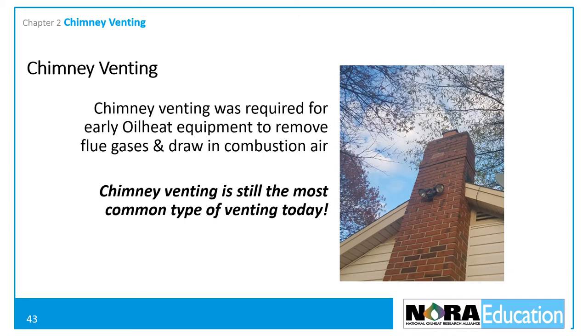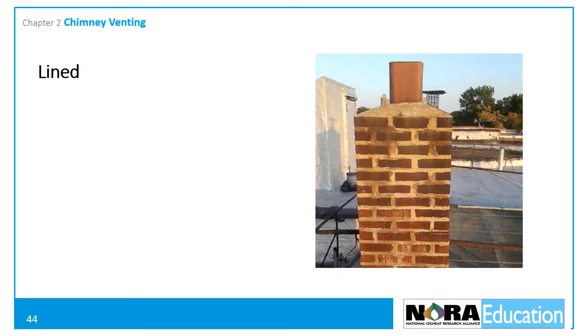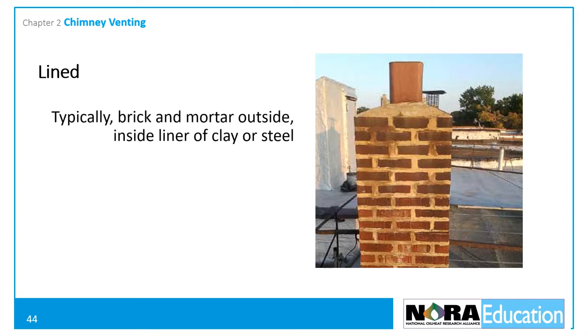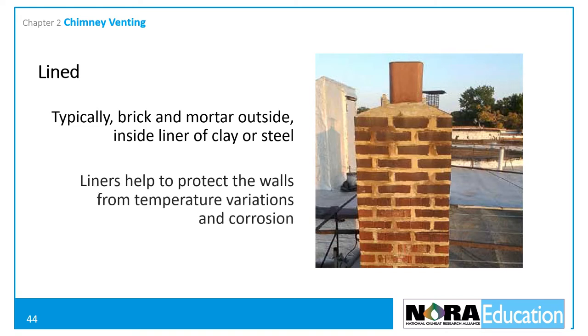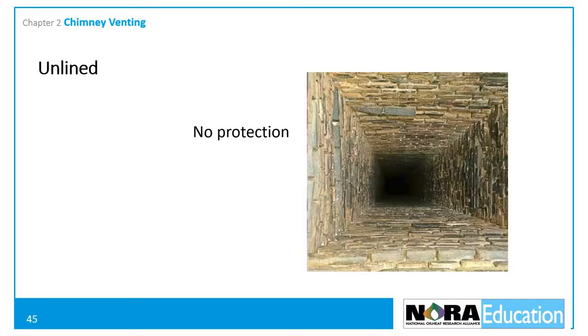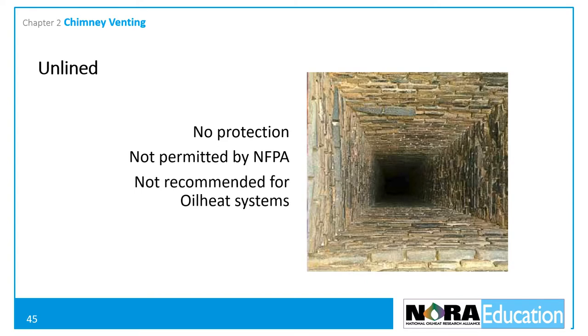Chimneys can be lined or unlined. A lined chimney is typically made of brick and mortar on the outside with an inside liner of clay or stainless steel. The liner protects the chimney walls from temperature variations and corrosion. An unlined chimney provides no means of protection for the chimney walls; they are not permitted under current NFPA regulations and are not recommended for oil heat systems.